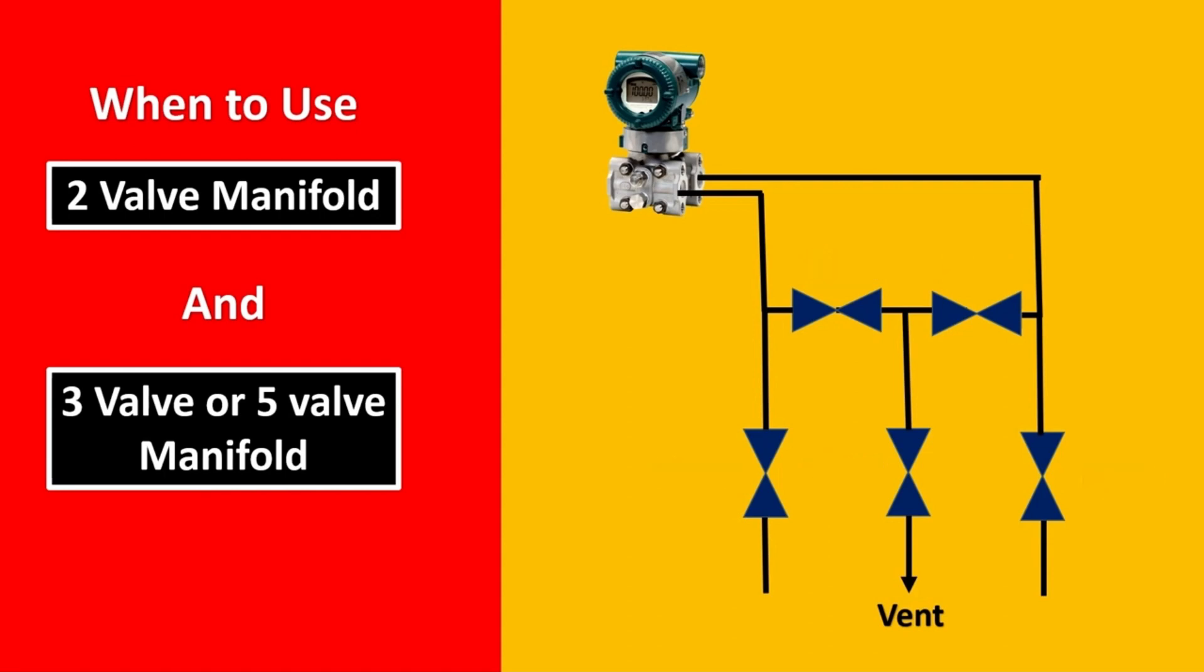Here in operation when you want to remove your transmitter, you would have to keep the extreme 2 valves closed and the middle 3 are going to remain open. So, the first 2 would equalize it and the third one would vent it out either to a closed system or to the atmosphere. 5-way manifold is specially used when you want to drain it.